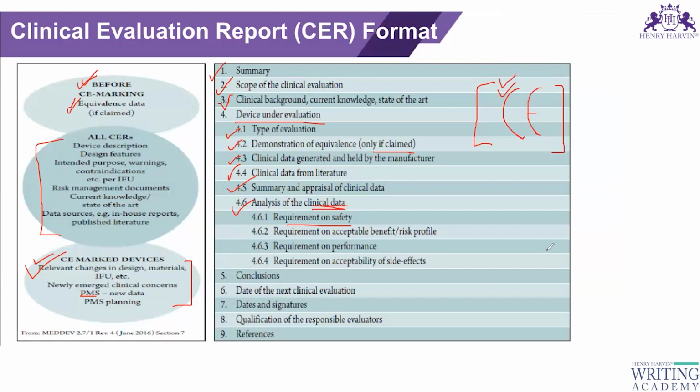that 1 year gap should be given as the date of next clinical evaluation. In case the device is already placed in the market and has completed a time span of at least 5 to 10 years, and there are no adverse effects reported which are life-threatening or very frequent or very serious, then the clinical evaluation can be submitted once in 2 years or once in 5 years, as per the instructions given by the regulatory authorities.